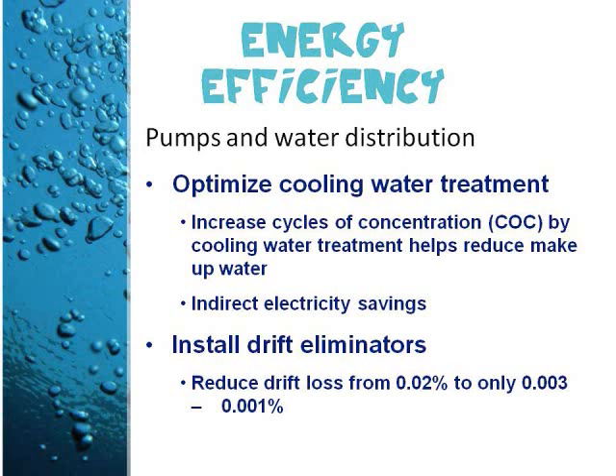In choosing pumps, of course, we want high efficiency pumps. In the optimization of cooling water treatment, it is mandatory for any cooling tower independent of what film media is. With increasing cost of water, efforts to increase cycles of concentration, or COC, by cooling water treatment would help to reduce makeup water requirements significantly. In large industries and power plants, improving the COC is often considered a key area for water conservation.